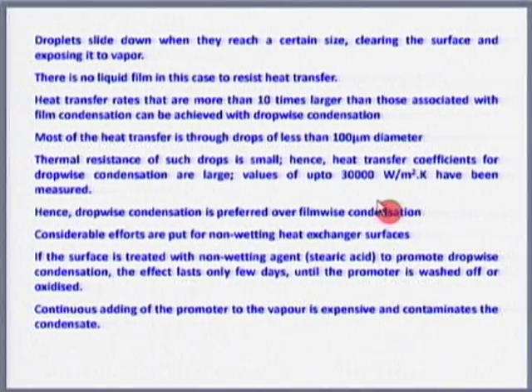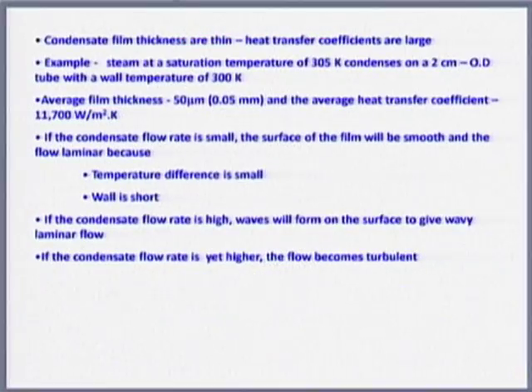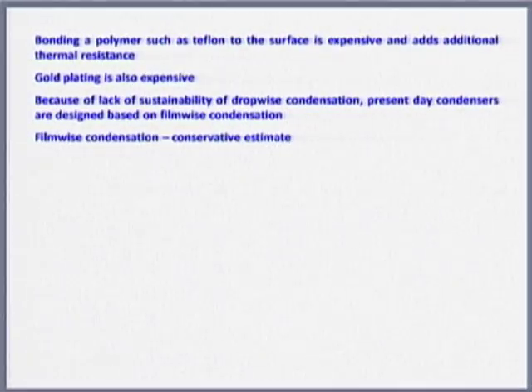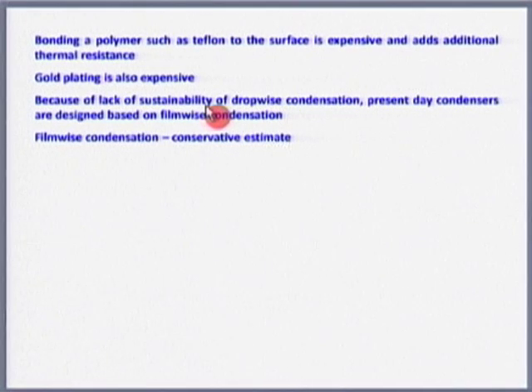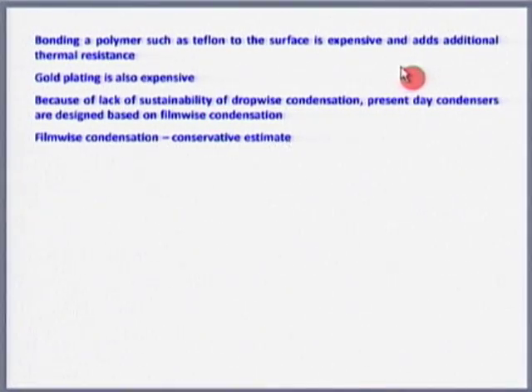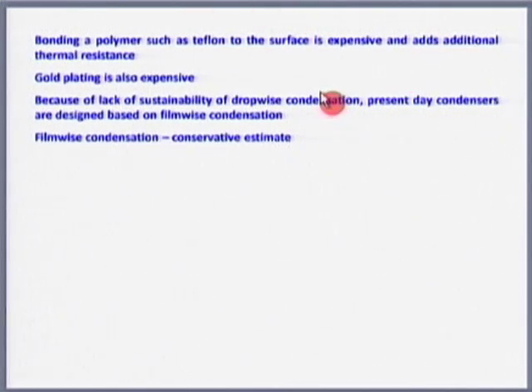It is better to design the condenser on the basis of film condensation so that it is a conservative estimate initially, and subsequently film condensation will take over. The main problem in dropwise condensation is sustainability — we cannot sustain it for long. Eventually dropwise condensation transits into film condensation because of wettability. Teflon coating gives dropwise condensation, but the coating vanishes. In fact, there are thousands of patents only on coatings to maintain dropwise condensation as opposed to film condensation.